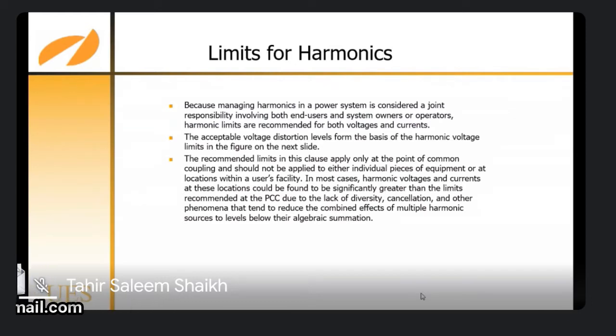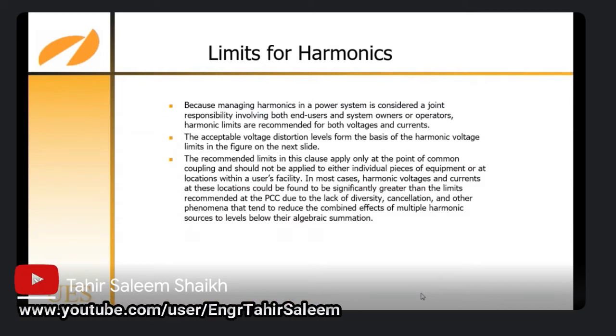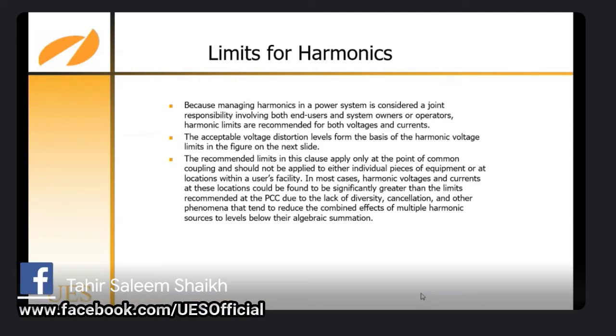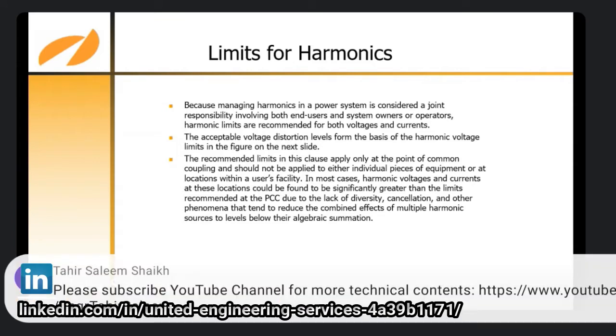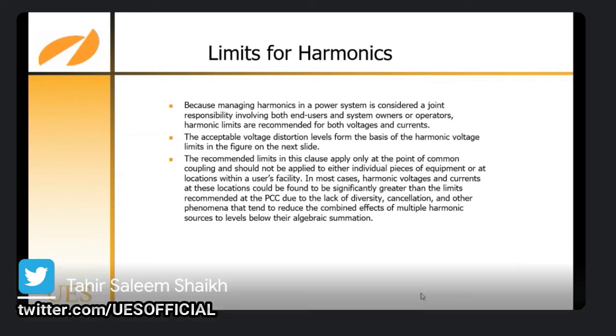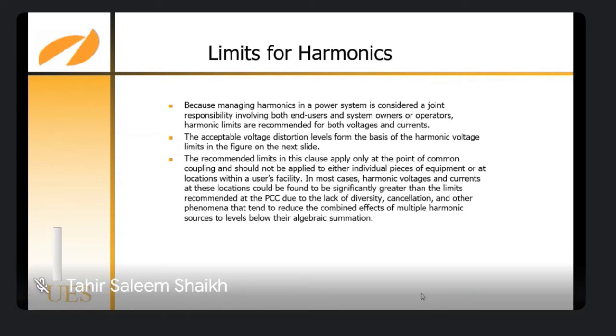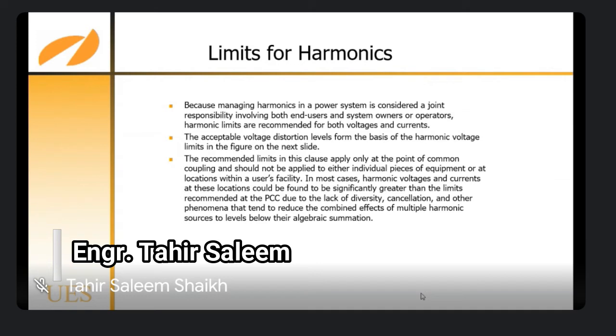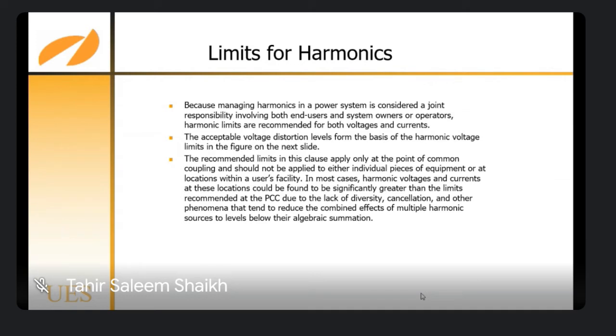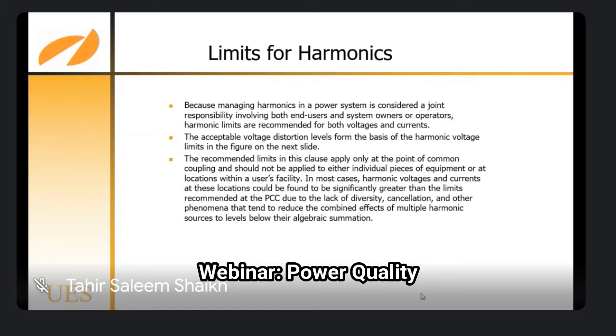The acceptable voltage distortion levels are the basis of the harmonic voltage limits in the figures on the next slide. The recommended limits in this clause apply only at the point of common coupling and should not be applied to either individual pieces of equipment or at locations within a user's facility. In most cases, harmonic voltages and currents at these locations could be found to be significantly greater than the limits recommended at the PCC due to the lack of diversity, cancellation, and other phenomena that tend to reduce the combined effects of multiple harmonic sources to levels below their algebraic sums.